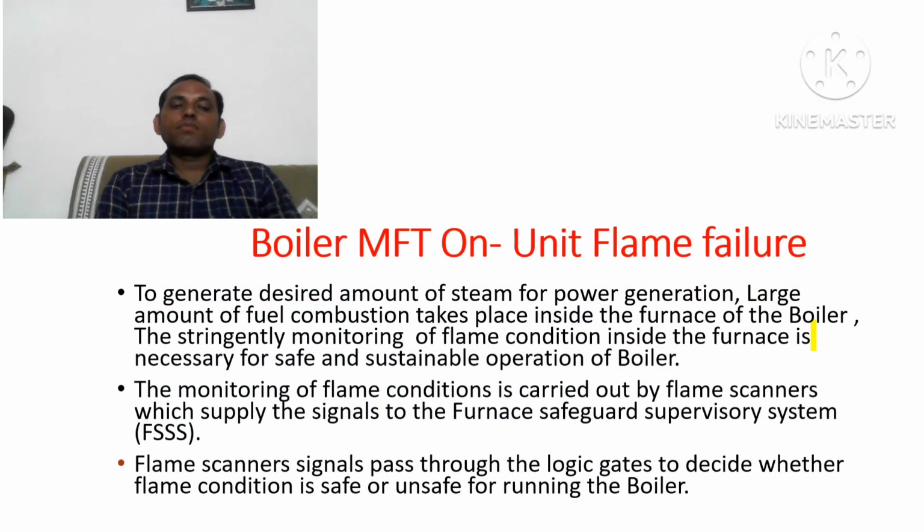New topic. This is one of the important boiler protections: boiler MFT on unit flame failure. So let's start. To generate the desired amount of steam for power generation, a large amount of fuel combustion takes place inside the furnace of the boiler. Stringent monitoring of flame conditions inside the furnace is necessary for safe and sustainable operation of the boiler.